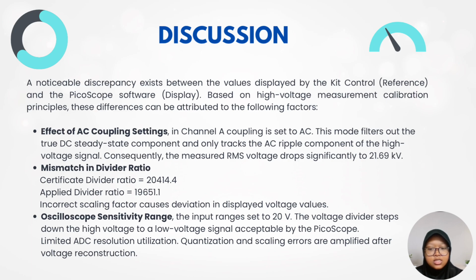The second factor is the divider ratio mismatch. The certified divider ratio should be 20414.4, but during the test it was changed to 19651.1. Since the PicoScope calculates high voltage by multiplying the measured low voltage signal with this ratio, any change directly affects the displayed voltage.